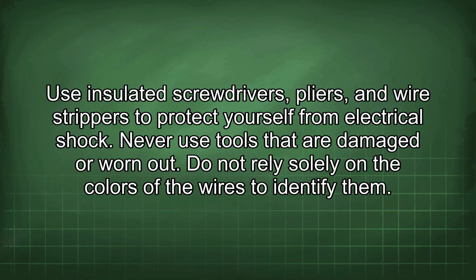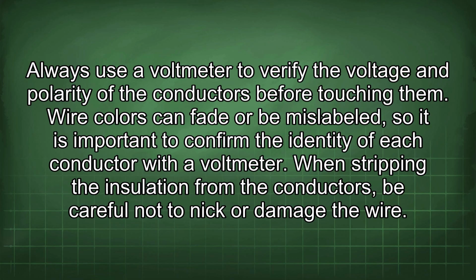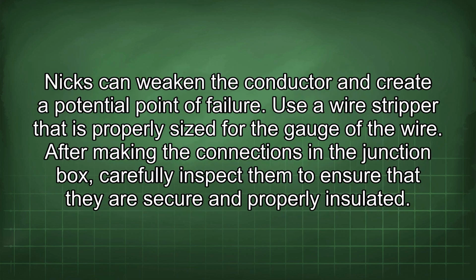Do not rely solely on the colors of the wires to identify them. Always use a voltmeter to verify the voltage and polarity of the conductors before touching them. Wire colors can fade or be mislabeled, so it is important to confirm the identity of each conductor with a voltmeter. When stripping the insulation from the conductors, be careful not to nick or damage the wire. Nicks can weaken the conductor and create a potential point of failure. Use a wire stripper that is properly sized for the gauge of the wire.